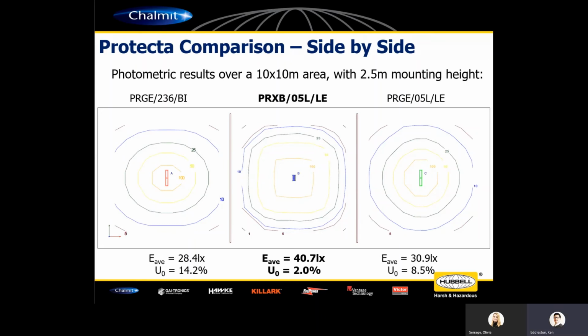The downside of that, however, is you have less control over where that light is going. So you will find that in a fluorescent product, some of that light is being emitted up into the sky. Okay, essentially it's wasted light, spill light, leading to light pollution or sky glow. So we want to try and minimize that. Again, we're trying to encourage people to throw that light where it needs to go, utilize it efficiently, essentially meaning that you can reduce your overall power, overall product quantities, and have a more efficient solution across your facility. The other point I'd maybe like to highlight here, though, is that despite the fact that it's got a flat diffuser and it's very concentrated in this area, if you look at the yellow line, the 50 lux line, the Protecta X actually has the greatest coverage of 50 lux compared against all the other Protectas that I'm showing on here. Okay, so it actually has a greater spread of 50 lux than the LED version and the fluorescent models.